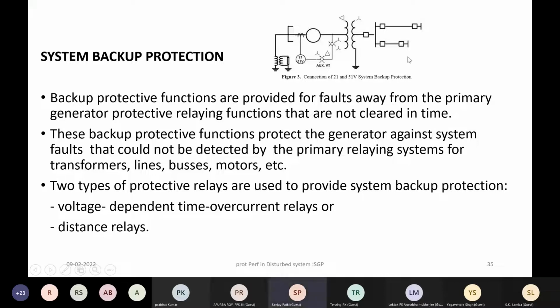So when the system disturbance takes place, there is also a risk that this impedance protection, which is zone 2 of that, which is reaching into this line, does not operate due to overloading or power swing condition. When the power swing phenomenon occurs, the impedance may move into the operating region of the zone 2 of the impedance relay, and that can cause malfunction. So again, this coordination becomes important.